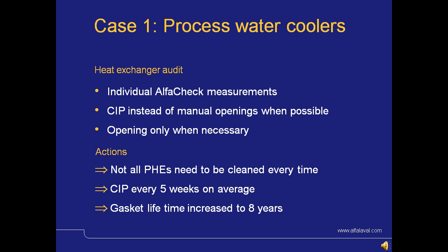The openings of the heat exchangers, if possible, will be done only when absolutely necessary. Not every time, but maybe every 3rd or 4th time if possible. The actions that this resulted in was that we saw that not all the PHEs need to be cleaned every time. Some of them got dirtier quicker than others, and this depends on the distribution in the piping. On average, the CIP needed to be done every 5 weeks, but the gasket lifetime increased to 8 years.